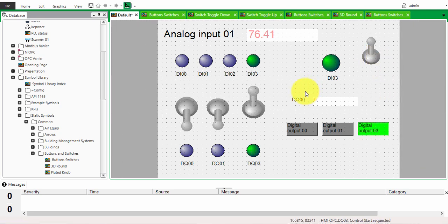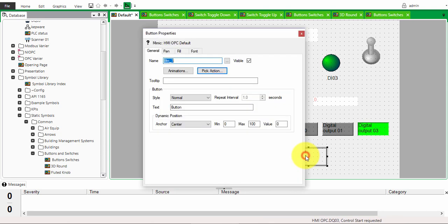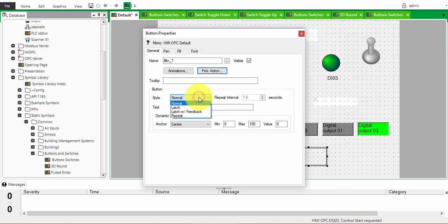The other thing I want to talk about is how to use the button. Go to Graphics and you'll find a button there — just draw it in your mimic. Double-click or right-click for animation. Under text you can type any text you want to show, so we'll call it 'Digital Value'. If you want separate start and stop buttons, use the normal push button style. If you want one button to toggle the same output on and off, use latch.